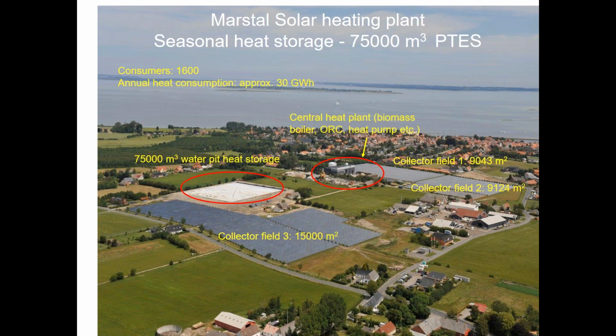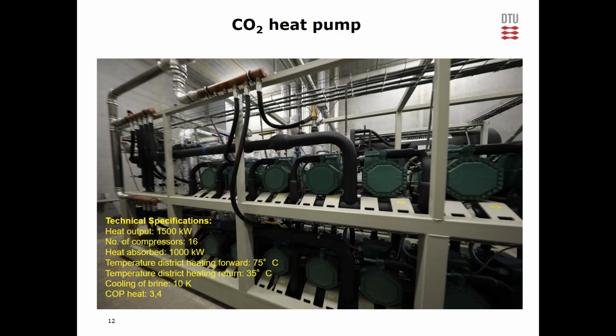I will share some of the monitored data of the system. First, I want to show you the heat pump: a CO2 heat pump with a heat output of 1.5 megawatts, and altogether 16 compressors. The district heating forward temperature is 75 degrees, and the return temperature is 35 degrees Celsius. The average COP for this heat pump is around 3.4 or 3.5.